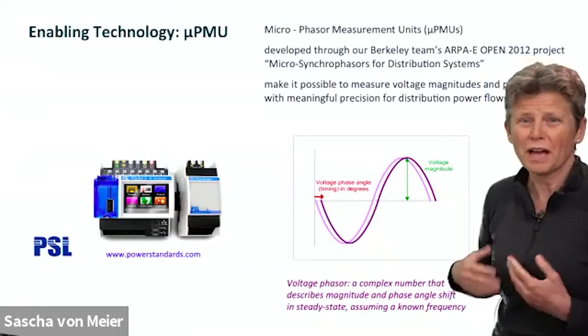And just to show you some illustrative data of what these measurements look like and how the voltage phase angle relates to power flows, here's an example from a field site where we tested these MicroPMUs. We're comparing the voltage phase angle between the substation on a distribution circuit and where a large photovoltaic array is connected. And so in blue, you see the amps, the current, that's roughly the power flow, the power that's being exported from what is obviously sunshine.